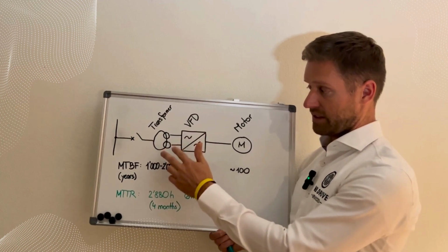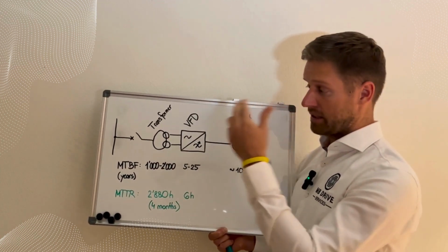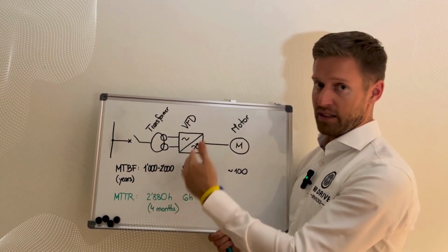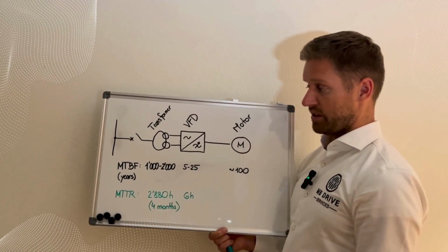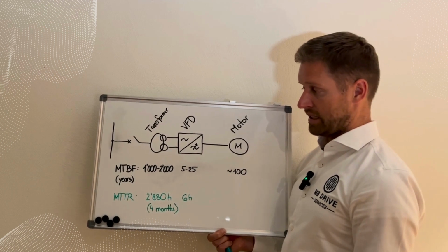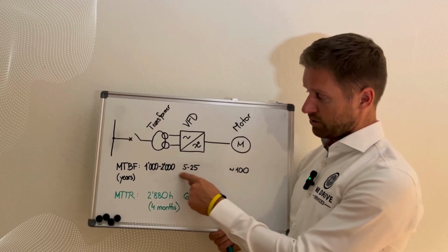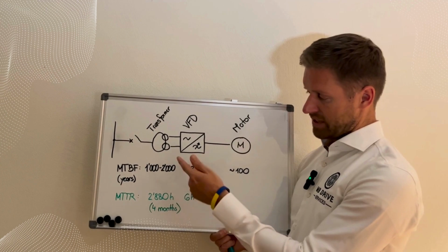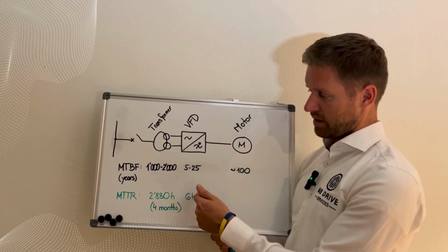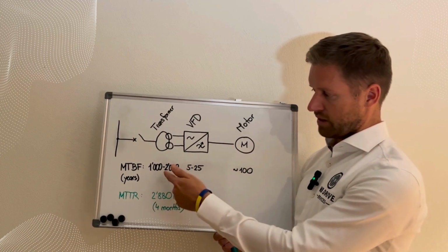If the failure is very severe, maybe the transformer is even damaged beyond repair, and a new unit needs to be manufactured. The VFD has a much shorter MTBF, say 5-25 years, so we are a factor of 100 times lower.